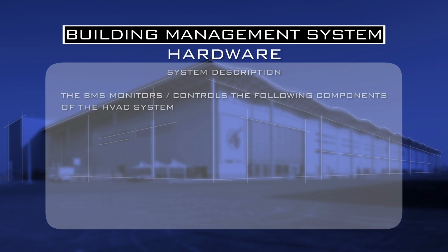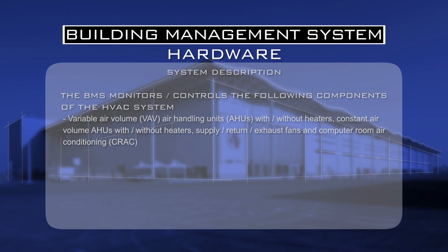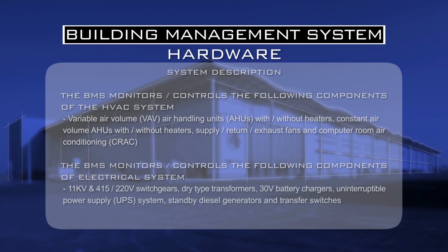The BMS monitors and controls the following components of the HVAC system: variable air volume or VAV air handling units or AHUs with or without heaters, constant air volume AHUs with or without heaters, supply, return and exhaust fans, and computer room air conditioning or CRAC. The BMS monitors and controls the following components of the electrical system: 11 kV and 415 and 220 volt switchgears, dry type transformers, 30 volt battery chargers, the uninterruptible power supply or UPS system, standby diesel generators, and transfer switches.